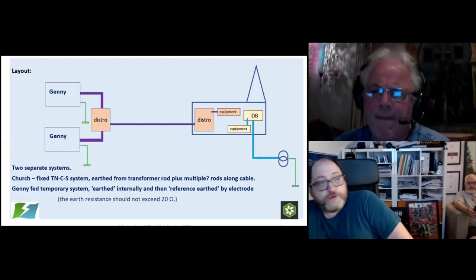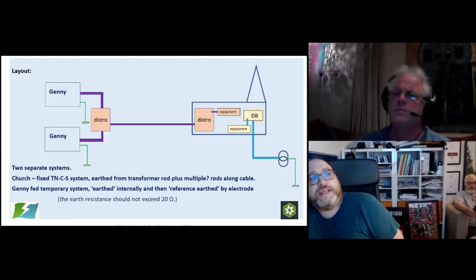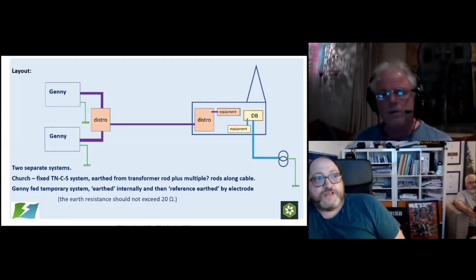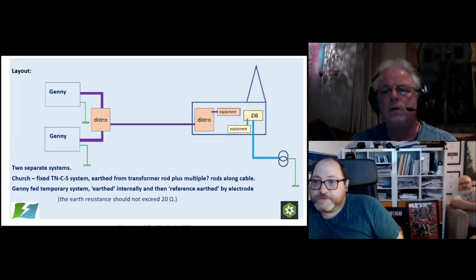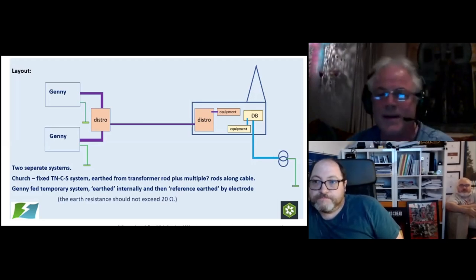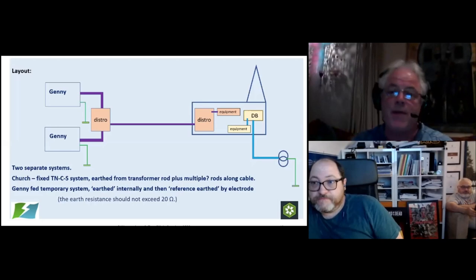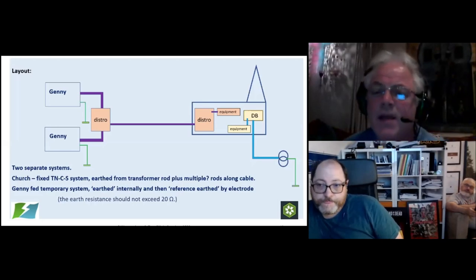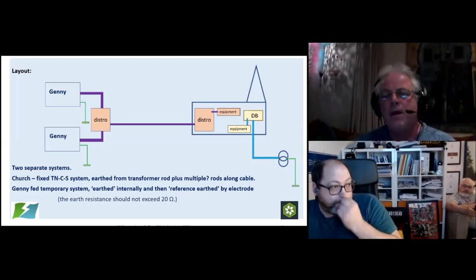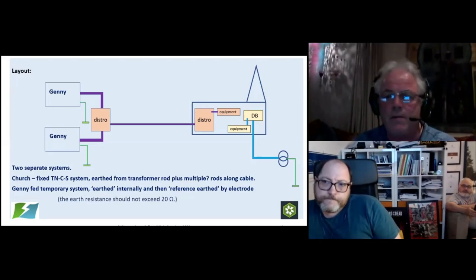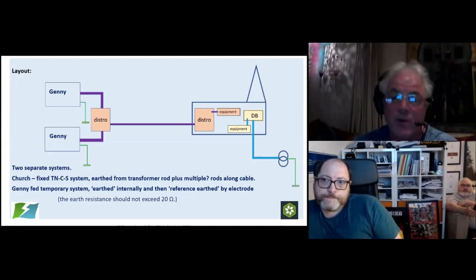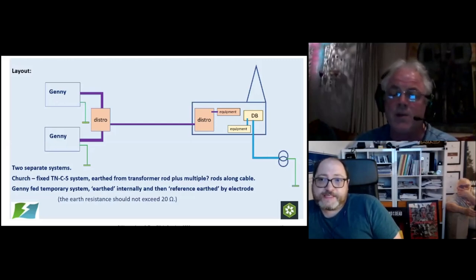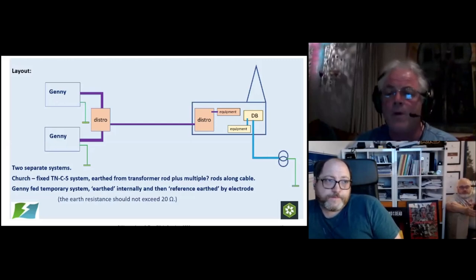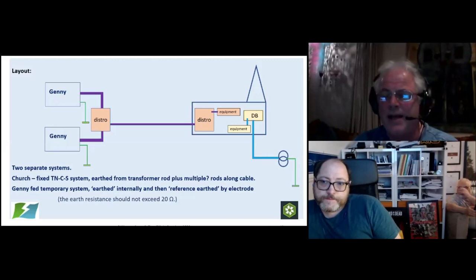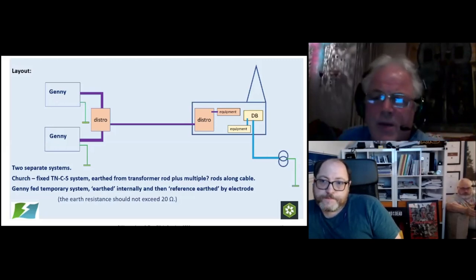Okay, another question from Sean. Is there any necessity for different RCD types on temporary systems? Well, we've already covered the fact that they should be type A. That is what is recommended under 7909. Unfortunately, a lot of the distro that's been kicking around for a while and is still being made, we still see it, don't we? We still see it being made with type AC. What can you do about that? Well, very little. The trouble is, we never know what's going to be plugged into them. And this is the issue.